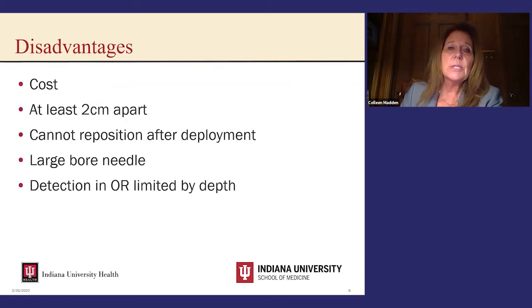What are the disadvantages? Probably the most significant disadvantage is cost. It's not inexpensive. The lesions and the tags that you place them in have to be at least 2 centimeters apart. If you place one inadvertently in the incorrect area, there is no repositioning after deployment. One disadvantage of the way the applicator system is made, it is a 12 gauge needle, so it's a larger needle than you typically use for localization. And then there are issues with the depth, and I'll let Dr. Blackwood address those.